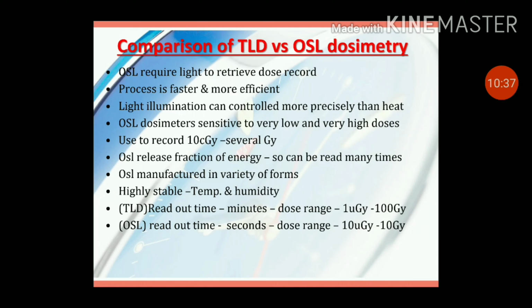They are typically 5 mm in diameter and 0.9 mm in thickness, and they are ideal to use for low dose measurement. Another advantage is that they can be annealed at a high temperature to empty the deep electron and hole traps. OSL intensity, curve shape and dose response may vary from dosimeter to dosimeter.